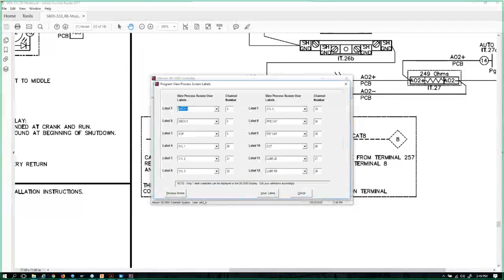Again, the only purpose this section serves nowadays is for the channels that we want to data log, and it works the same way. We simply select the channel that we want to data log, and as soon as we click into the next box, if we change it, and of course I didn't change it just now, the channel number assignment will also change automatically. If your name is 9 characters or greater from the channel setup section, this section here limits you to 7 characters max. So it'll simply give you a little warning, like a slap on the wrist, should you select a channel that has greater than 7 characters, but then it'll just cut off the last couple of characters. So again, the shorter names that you can come up with for these channel names, the better.